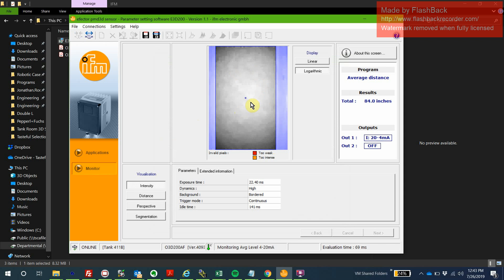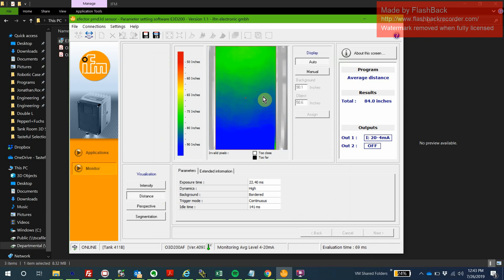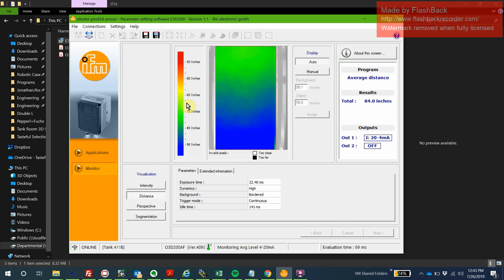What you're looking at here is what the sensor is actually seeing on a grayscale. You can actually click on Distance to see a little bit more color added. The blue is farthest away from the sensor, meaning this blue section is empty. As the distance between the pile and the sensor decreases, that pile is growing. This is our peak here, roughly 75 inches from the sensor.